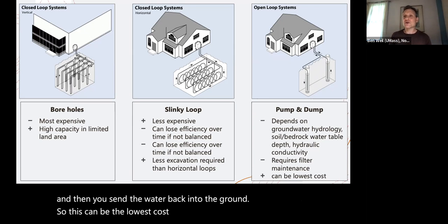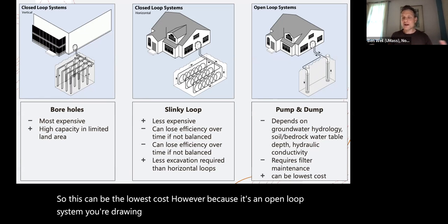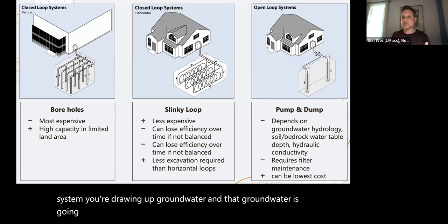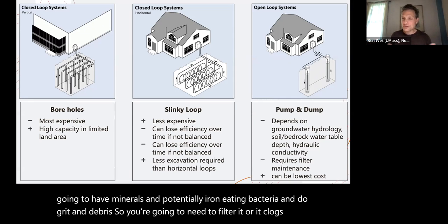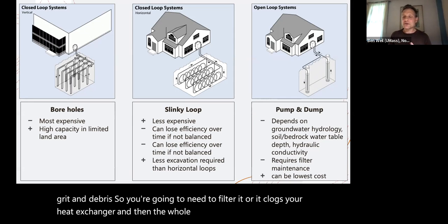However, because it's an open loop system, you're drawing up groundwater, and that groundwater is going to have minerals and potentially iron-eating bacteria and grit and debris. So you're going to need to filter it, or it clogs your heat exchanger, and then the whole thing goes bad. So it does tend to require filter maintenance.